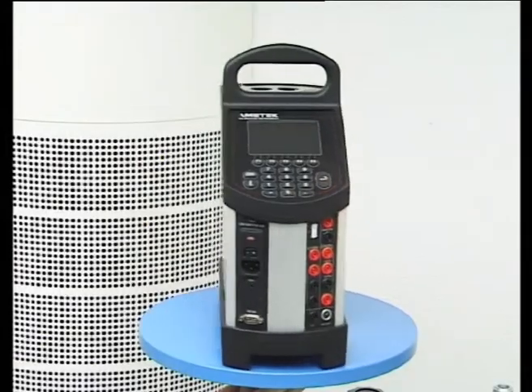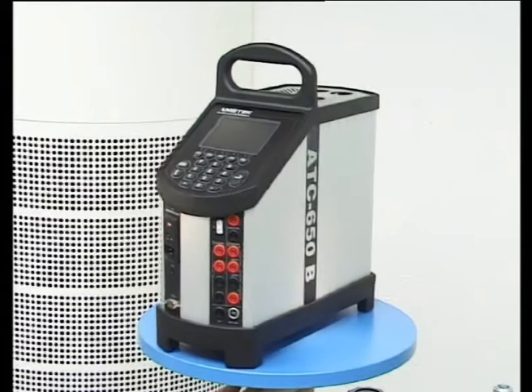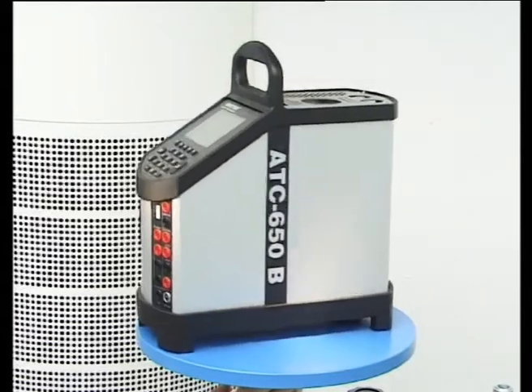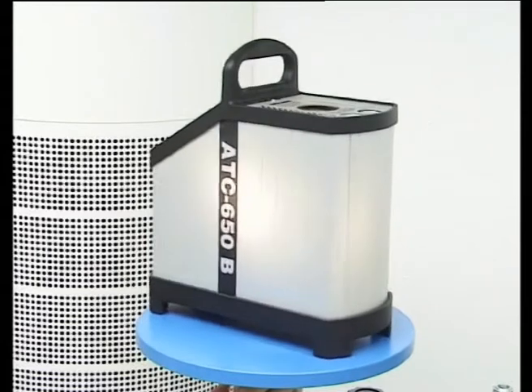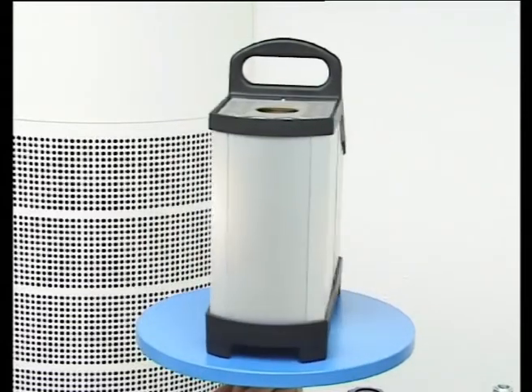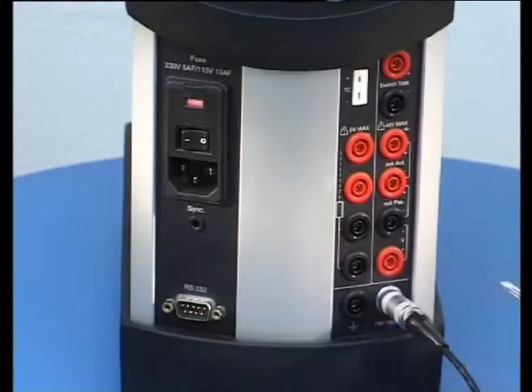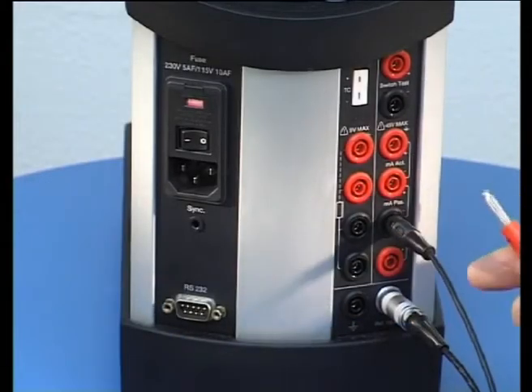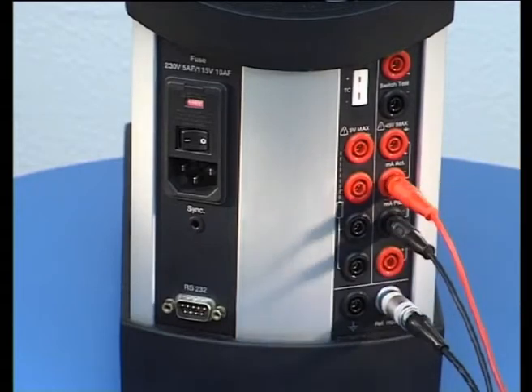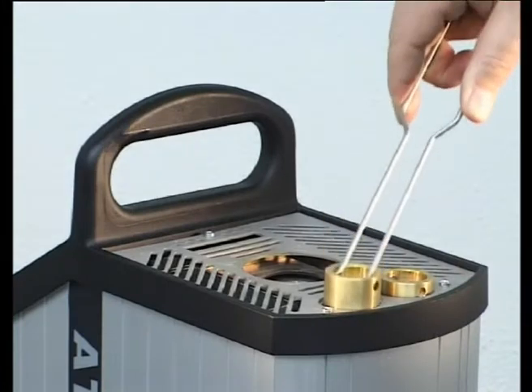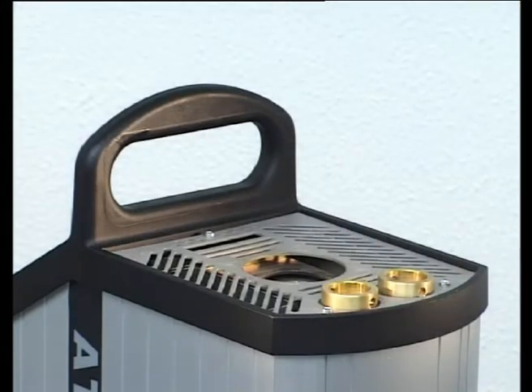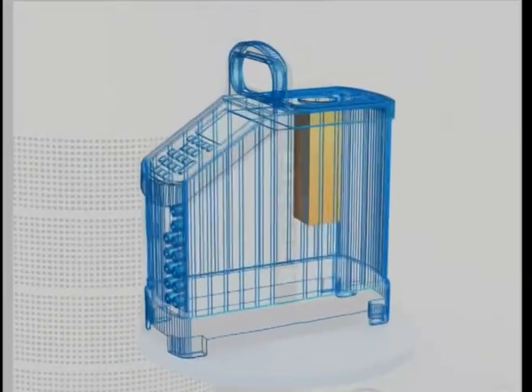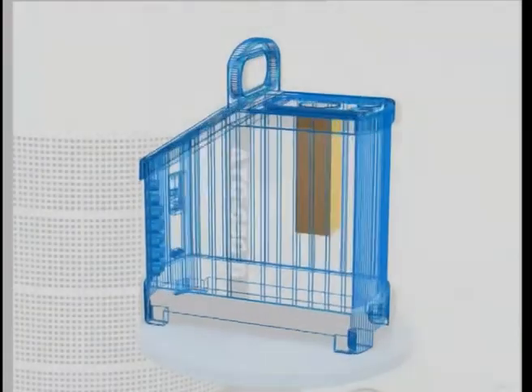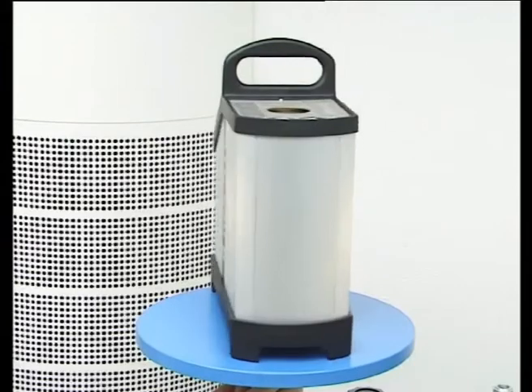To provide more flexibility in your work, we have focused the design of the ATC series on functionality and quality. The display and keyboard are angled, making them easy to use on a benchtop or in a difficult space. Everything is operated via the front panel and the heat source is positioned furthest from your hands and face. A practical and convenient storage area is located behind the heat source. The calibrator is constructed of rigid aluminum plates mounted on strong upper and lower castings, providing the best combination between weight, strength, and stability.